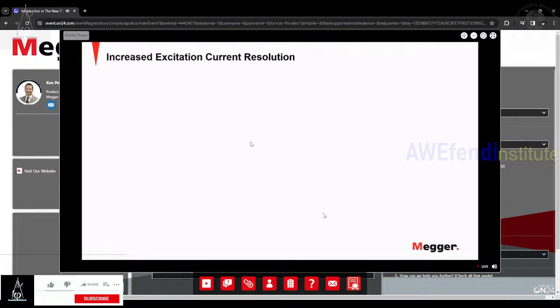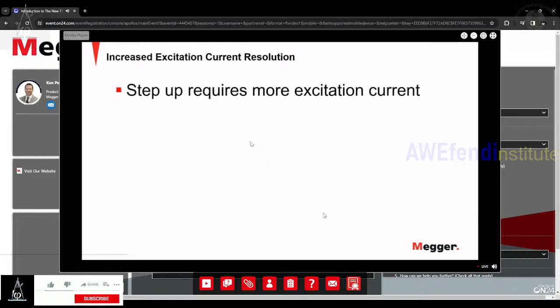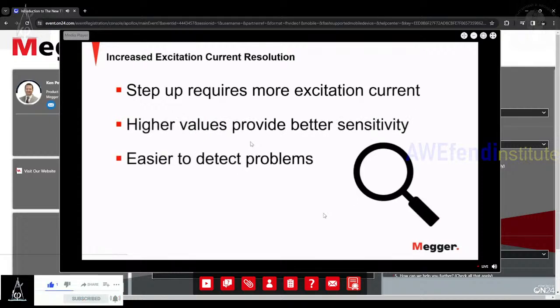And with this increased excitation current resolution that we get from injecting on the secondary, because now instead of voltage we need current, the way the transformer works, that gives us an easier, in-depth dive into that excitation current to really look for differences. When you're doing a step-down measurement, you may only draw a few milliamps, whereas by injecting on the secondary, you're going to see that secondary current being required as part of that ratio transformation. And with those higher excitation values, it'll be easier to see when a certain phase may be having a problem.